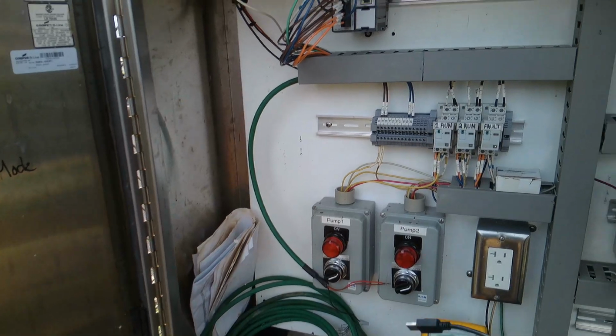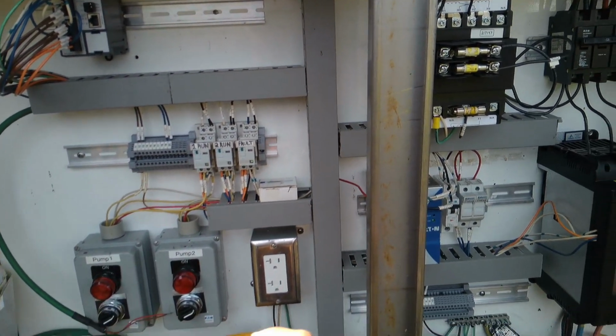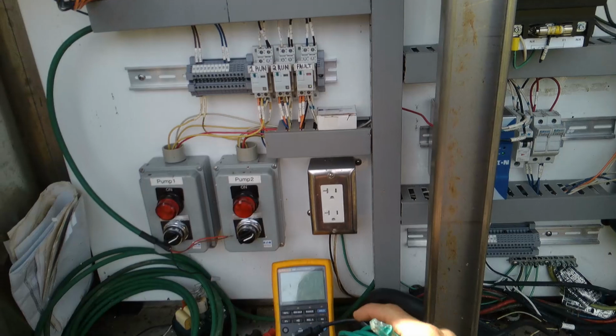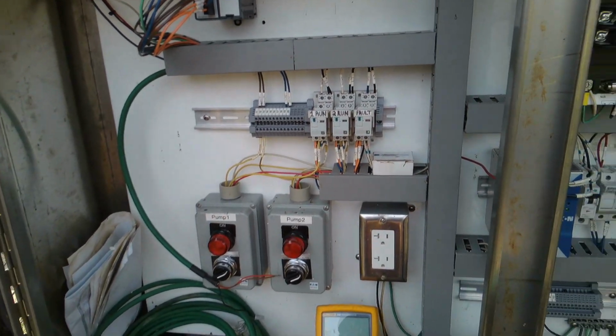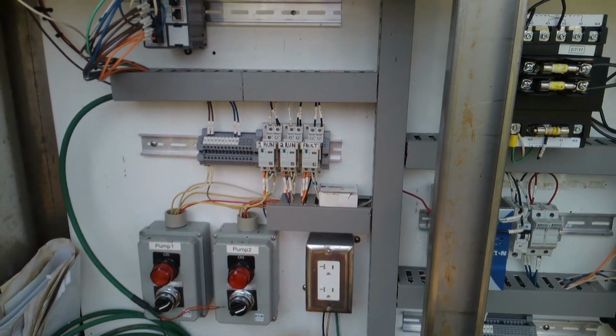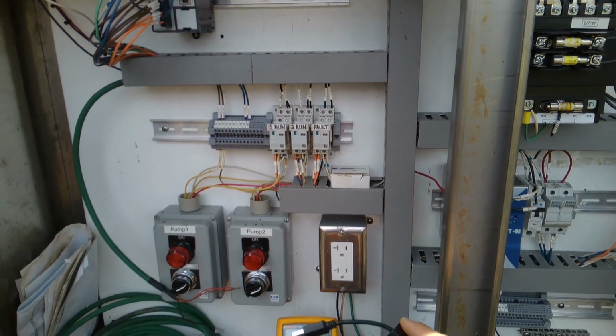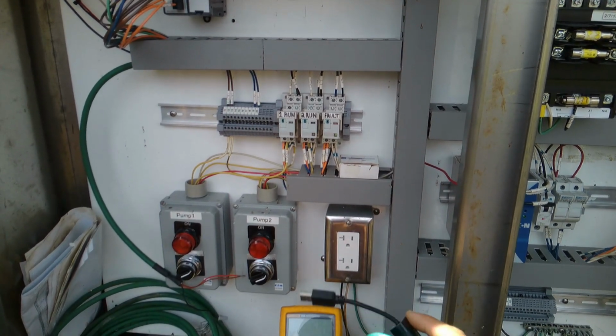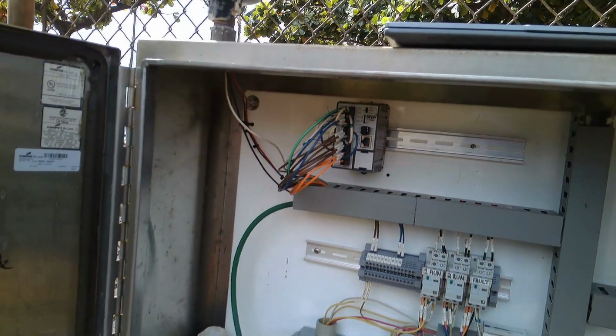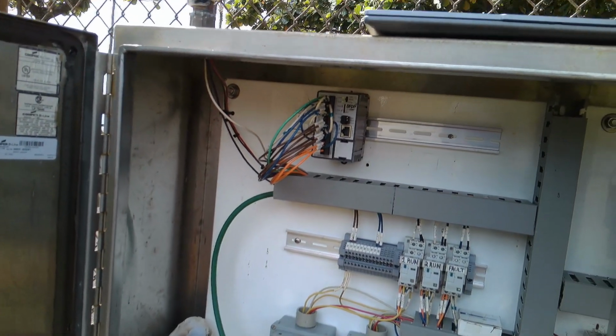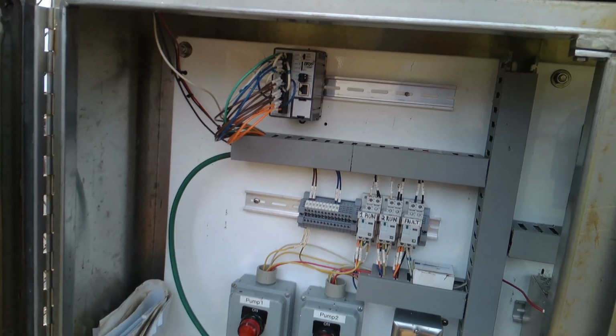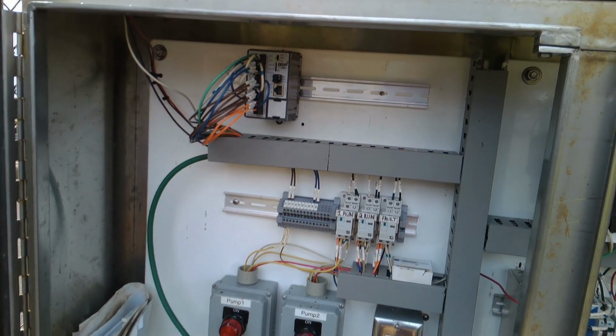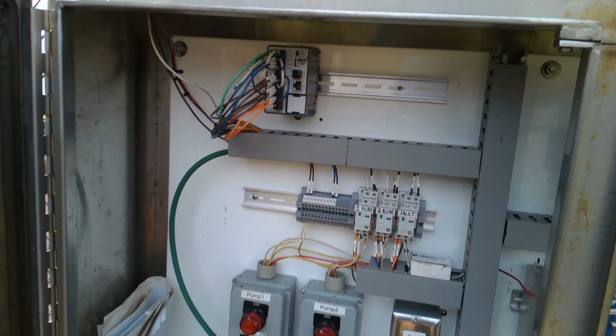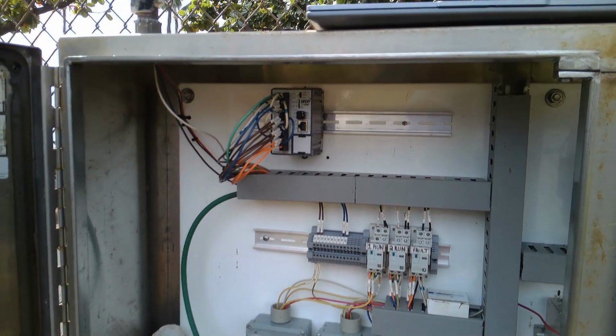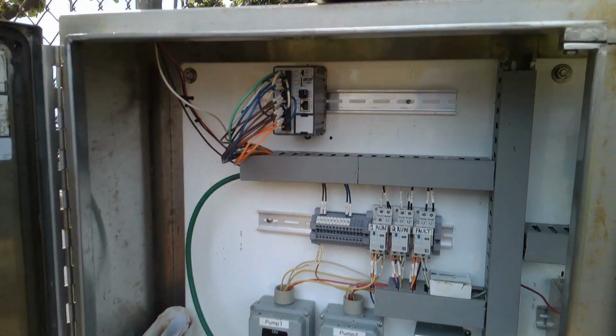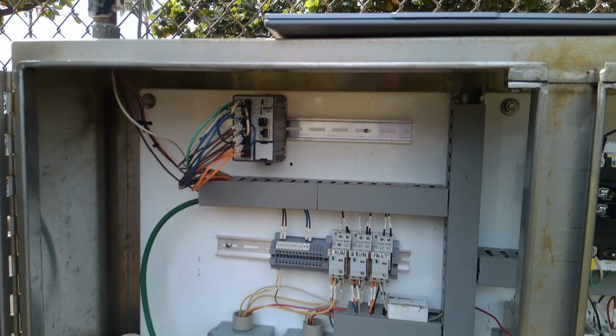This failure mode on the transducer is remarkable in that instead of failing to 0 milliamps or a dead short and having greater than 24 milliamps, it's failed right in a tight little bandwidth, and the signal is bouncing like crazy. So that's a dangerous failure, because the PLC didn't think the transducer signal was a problem. It thought the sump or the wet well level was actually bouncing that much.